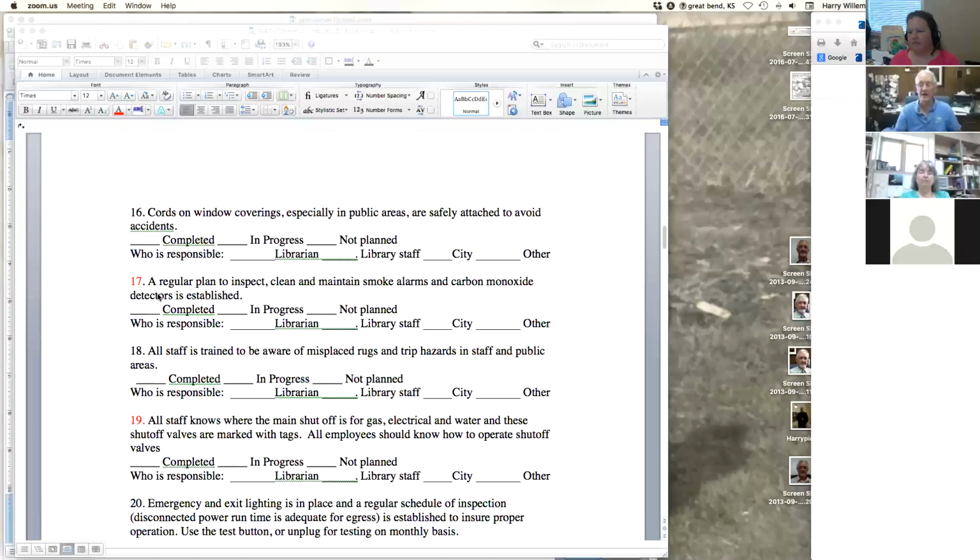They work on batteries, and if it's been in for 5 or 6 years, on the emergency lights, the batteries might not even carry a charge at all. So you need to replace the little batteries in them. Smoke alarms should be checked, and the battery, if it's battery operated, is supposed to be changed when you do the time change every year. So that's twice a year. Basically, mine at home, I do once a year with the time change and not twice a year, and that seems to work okay.